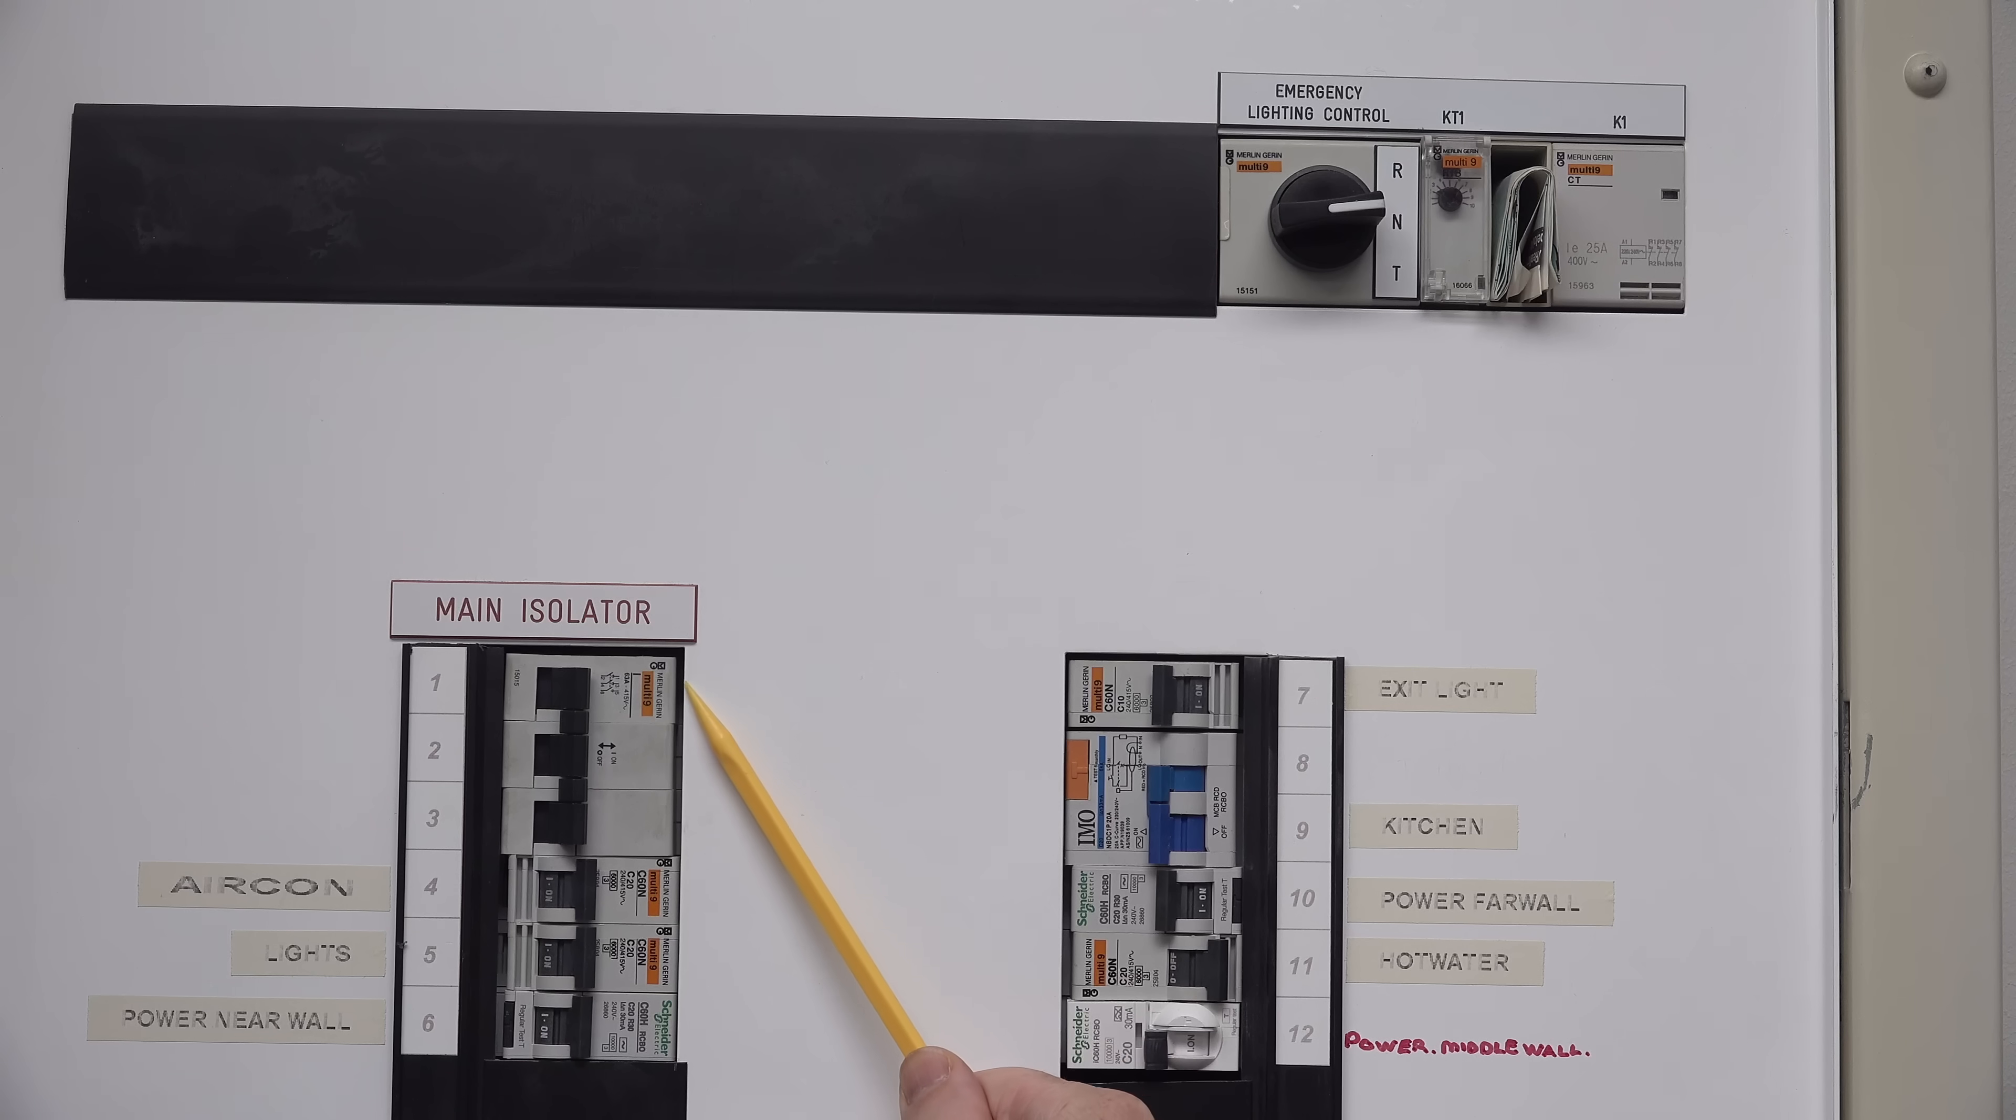Anyway, we've got the main isolator here. These are a Merlin brand. I haven't seen a Merlin in residential, but I don't know, maybe leave it in the comments down below. How do you rate Merlin? So I've obviously got three phases coming in here because there's three phases here. And then we've got an aircon breaker. We've got a light breaker. Neither of those are RCD, have an earth leakage or a residual current device in them.